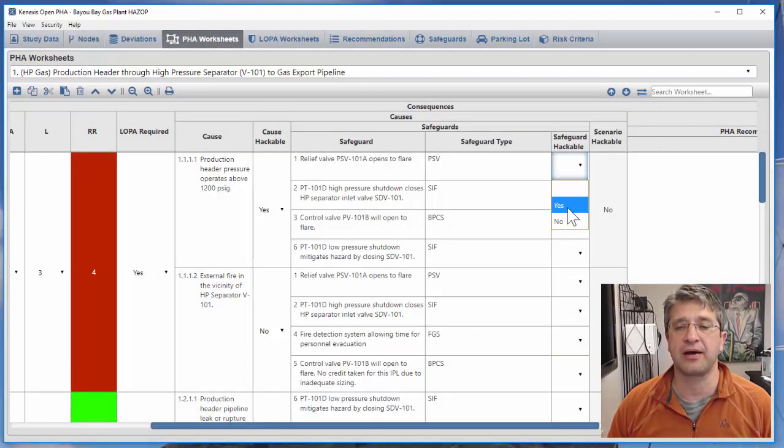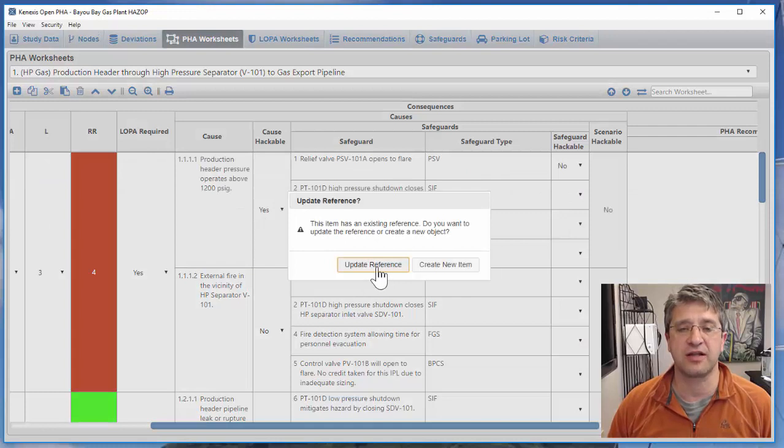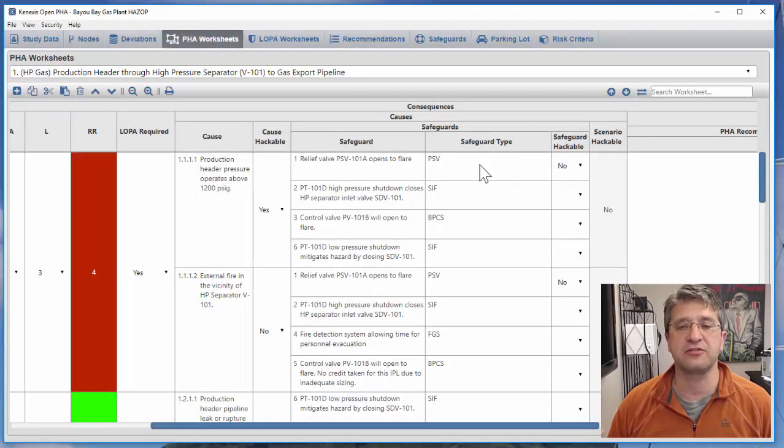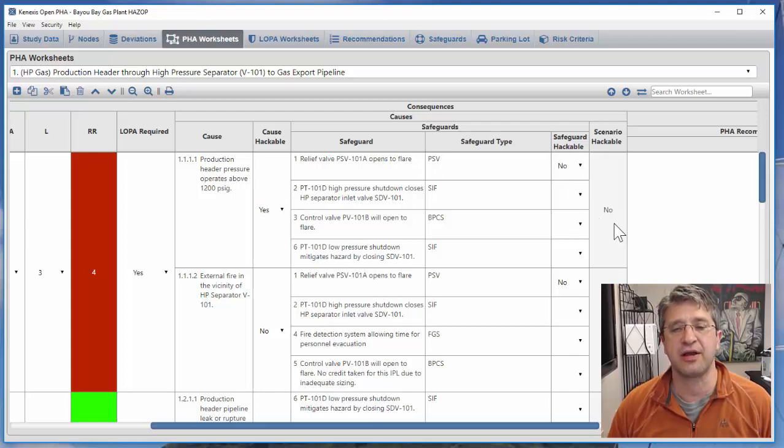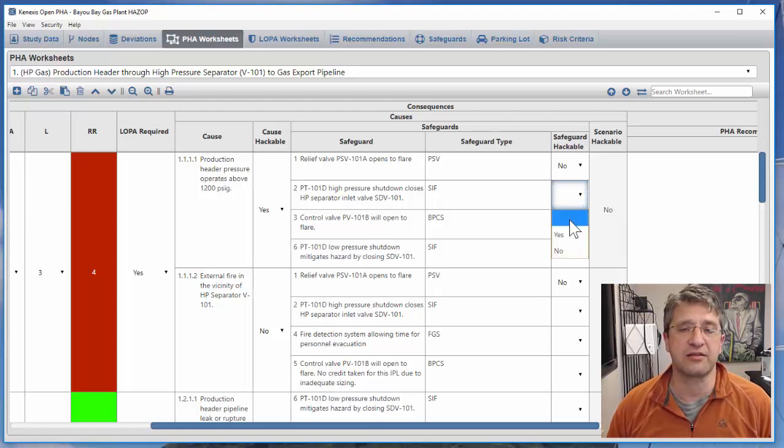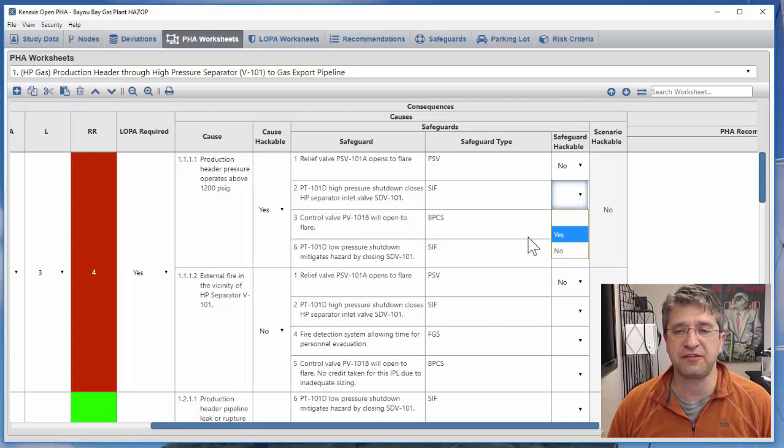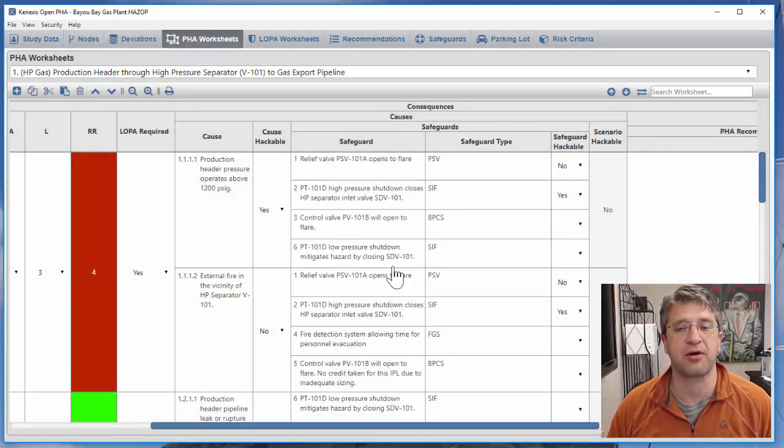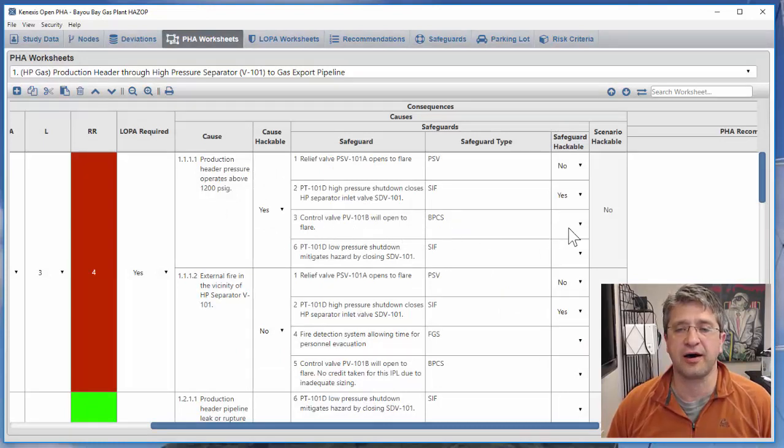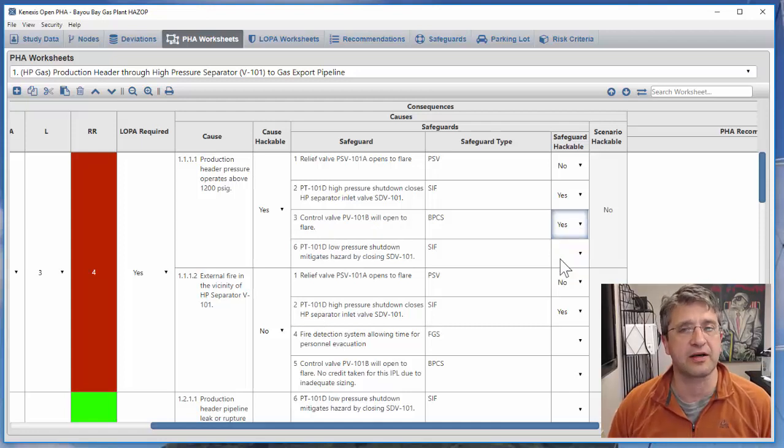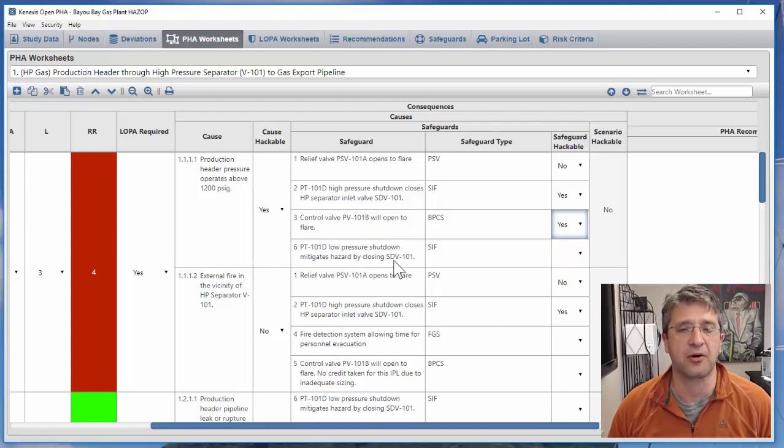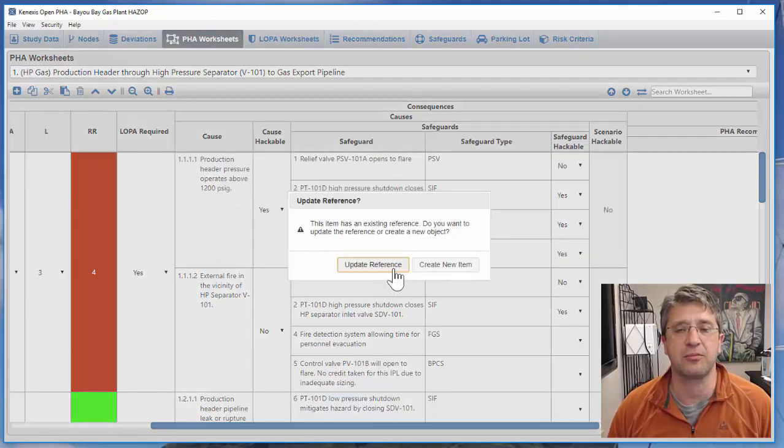I'm going to say that safeguard is not hackable, update reference, and because one of the safeguards is not hackable we know that the entire scenario is not hackable. We can continue on with the other ones and say things like a safety instrumented function is hackable because it resides in a processor with a routable protocol. Control valve as a basic process control loop, yes that is hackable. Low pressure shutdown is a safety instrumented function, yes that is hackable.